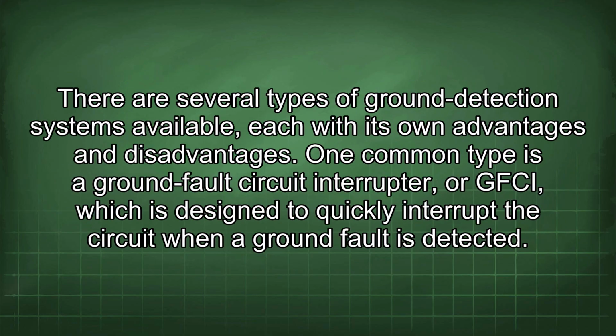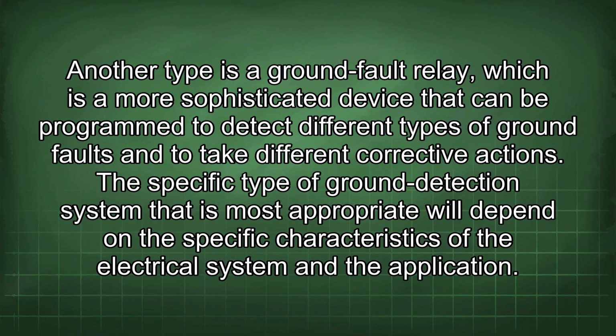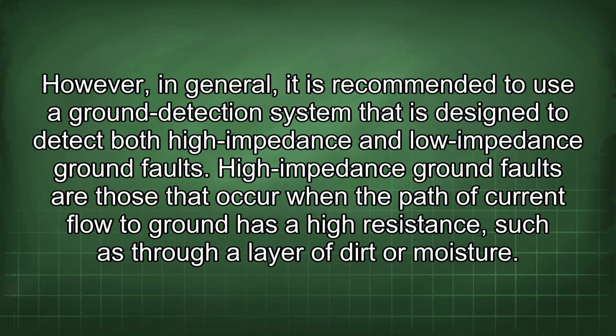There are several types of ground detection systems available, each with its own advantages and disadvantages. One common type is a ground fault circuit interrupter, or GFCI, which is designed to quickly interrupt the circuit when a ground fault is detected. Another type is a ground fault relay, which is a more sophisticated device that can be programmed to detect different types of ground faults and to take different corrective actions. The specific type of ground detection system that is most appropriate will depend on the specific characteristics of the electrical system and the application. However, in general, it is recommended to use a ground detection system that is designed to detect both high impedance and low impedance ground faults.